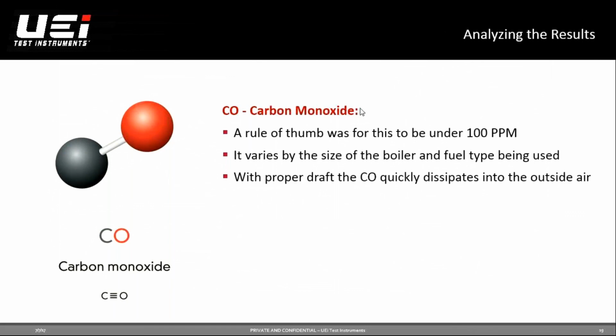The general rule of thumb for carbon monoxide going out the flue was actually 100 parts per million. Then on-demand hot water heaters came out and they started putting out upwards of 150 plus. So you always want to check what the specs are for the manufacturer, because it can vary on the size of the boiler and the type of fuel you're using. I know in the Northeast, I still see a lot of oil kits and combustion analyzers that have been used, so you just got to make sure you have it set on the right fuel, and that you're following whatever the manufacturer specs are. And as I mentioned earlier, it goes out the flue, and with the proper draft, that CO is going to quickly dissipate out into the air.